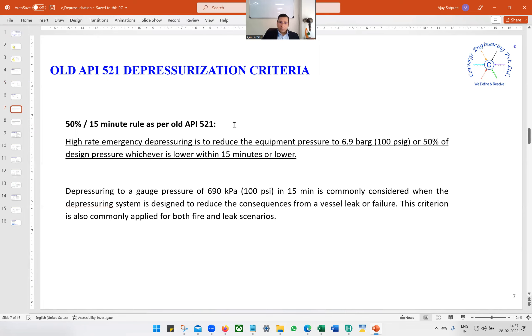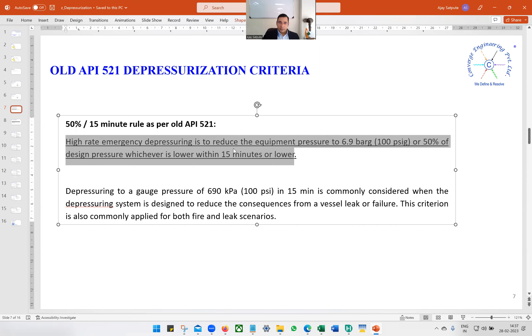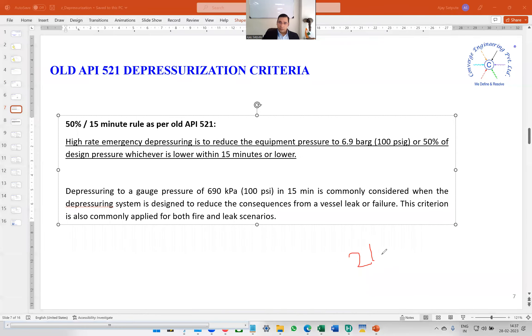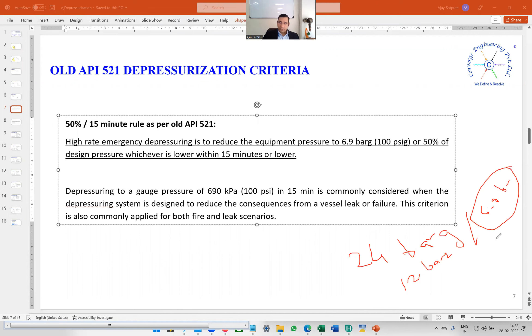In the old API 521, before the fifth edition, the 50%/15 minutes rule stated that you have to depressurize the equipment to 6.9 bar gauge or 50% of the design pressure, whichever is lower, within 15 minutes. For example, if a vessel has a design pressure of 24 bar gauge, you must depressurize to 12 bar gauge or 6.9 bar gauge — whichever is minimum. In this case, 6.9 is the minimum, so from 24 bar gauge you depressurize to 6.9 bar gauge in 15 minutes or less.